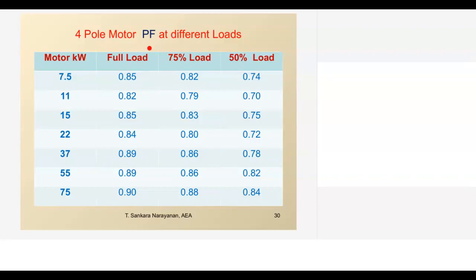So whenever a tong tester current reading is taken and we are measuring the kilowatt, we had better take the load power factor of the particular motor. See how much variation, 0.85 to 0.74. So this we have to keep in mind. That is why most of the suppliers will give this data even for 25% load. If we have that data, this can be used for exactly estimating the kilowatt reduction. Otherwise, we have seen some equipment suppliers measure the current and assume the power factor as 0.89, then they give so much kilowatt saving. So as an energy auditor or energy engineer, you have to review these types of calculations.